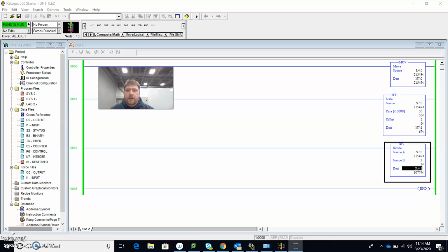is that we have a signal, a 0 to 10 volt signal. We're calling that our analog signal to our analog input. But that 0 to 10 volt signal is being converted to bits inside this PLC, right? That card is converting that to bits. The program sees it as bits, and that 0 is the same as 0 bits. The 32,767 is the same as 10 volts. So all that is, there's nothing special going on.